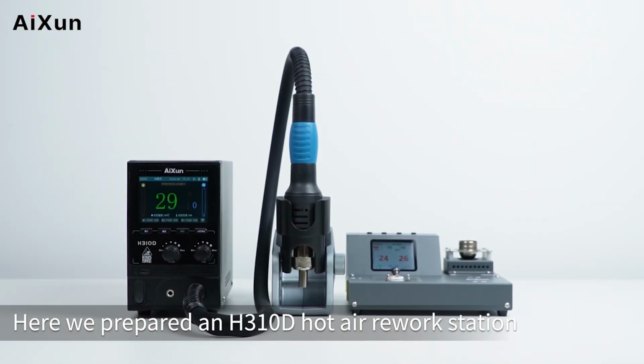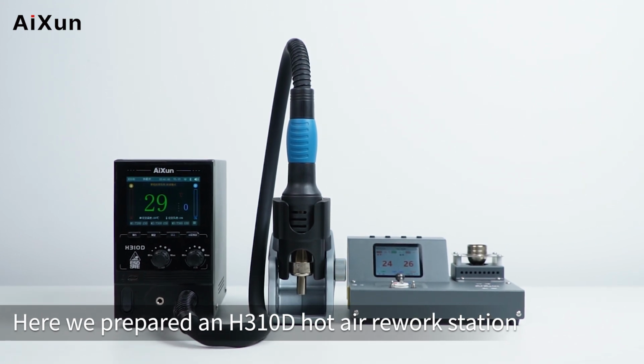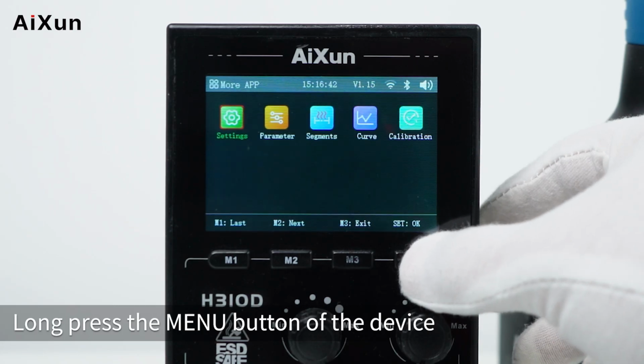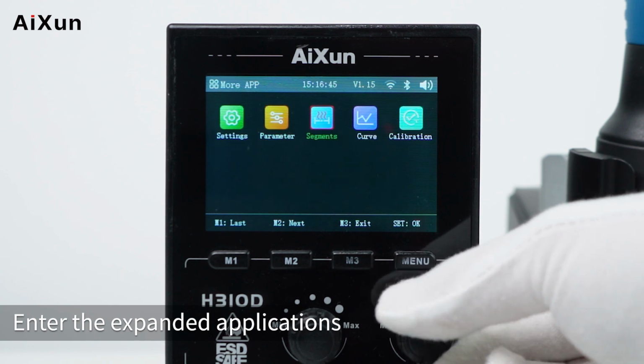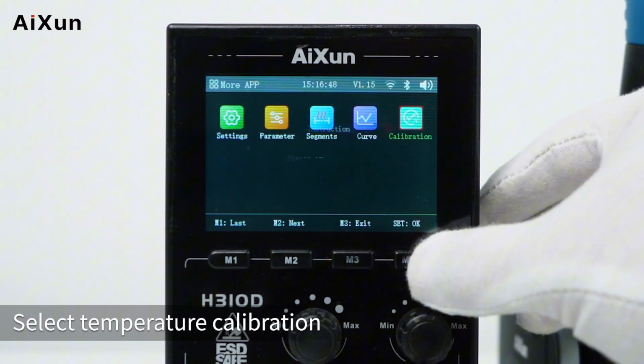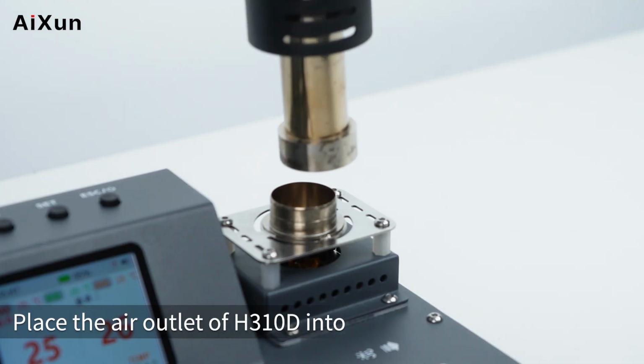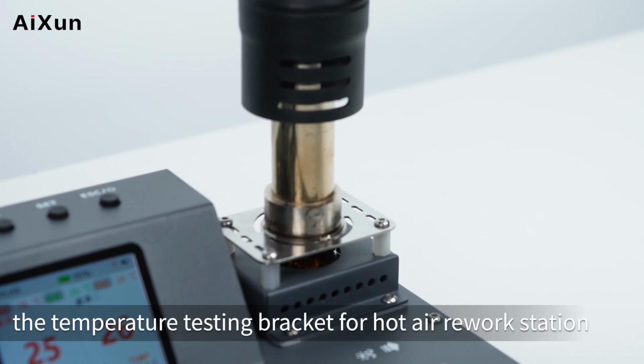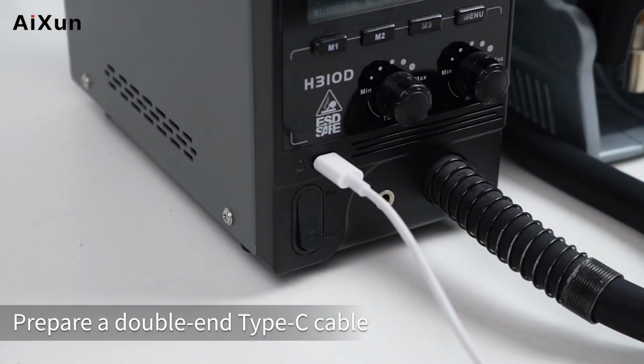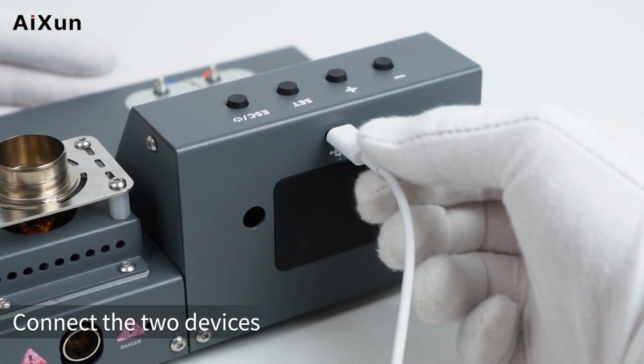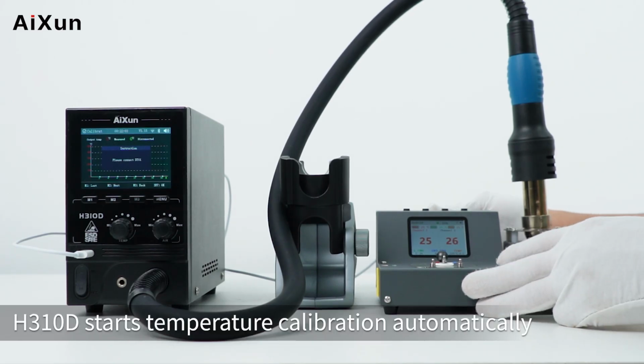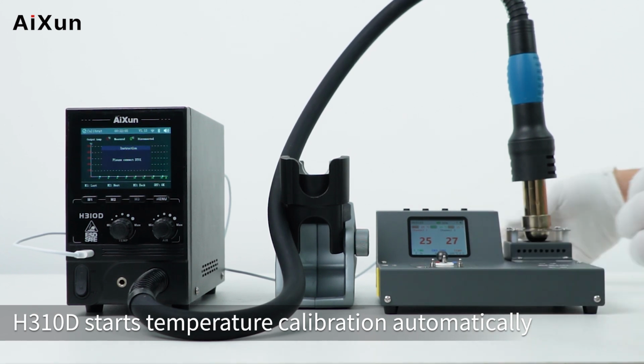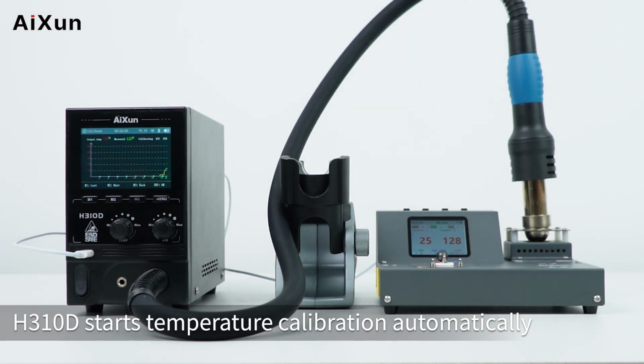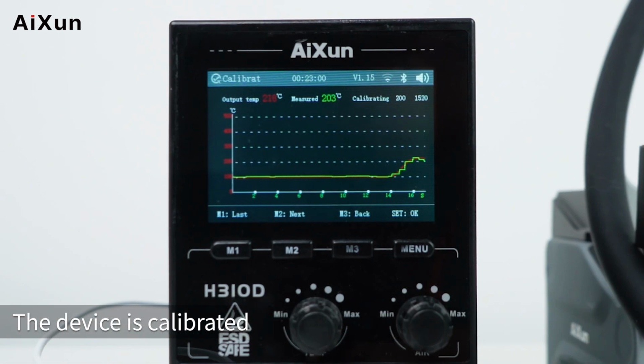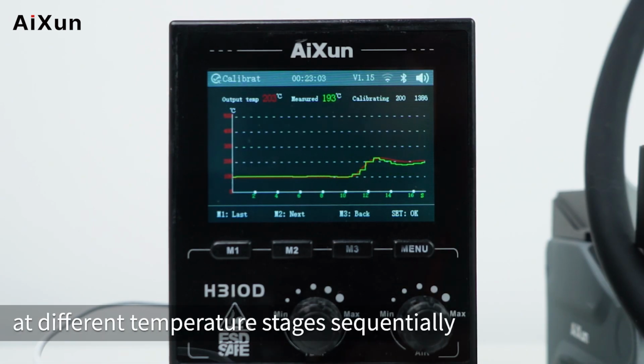Temperature measurement for hot air rework station. Here we prepared an H310D hot air rework station. Long press the menu button of the device. Enter the expanded applications. Select temperature calibration. Place the air outlet of H310D into the temperature testing bracket for hot air rework station. Prepare a double-end Type-C cable. Connect the 2 devices. After connection, H310D starts temperature calibration automatically. The device is calibrated at different temperature stages sequentially.